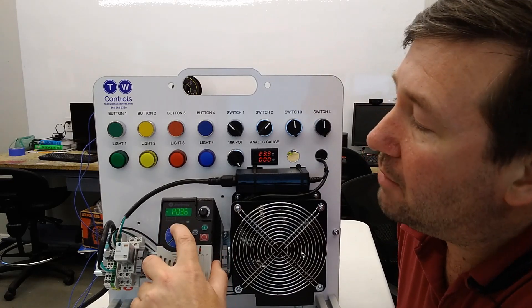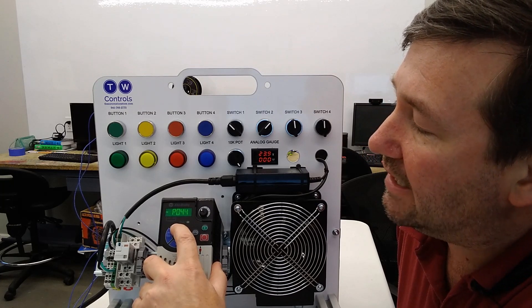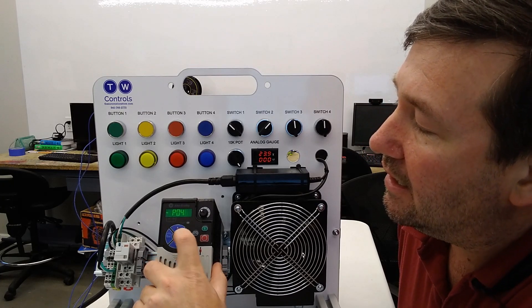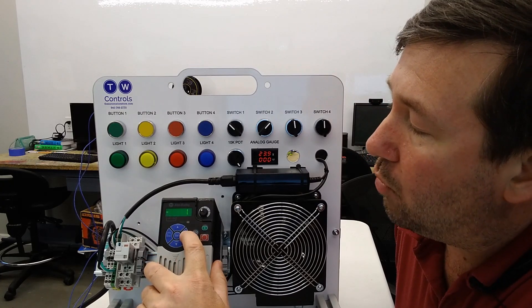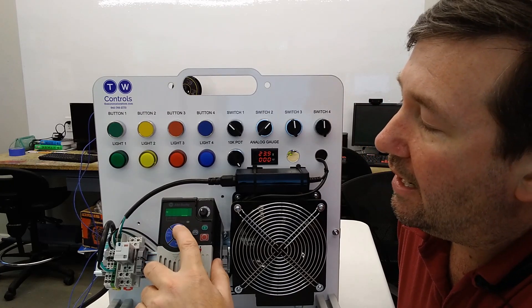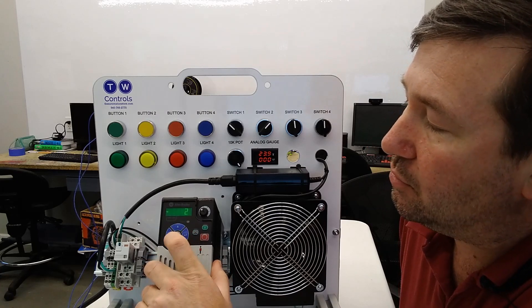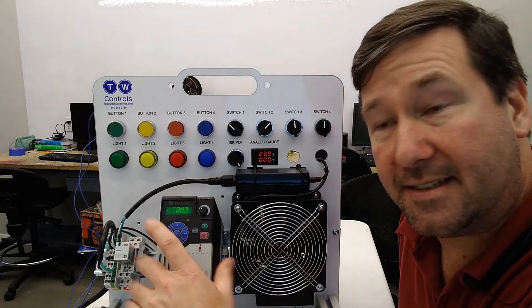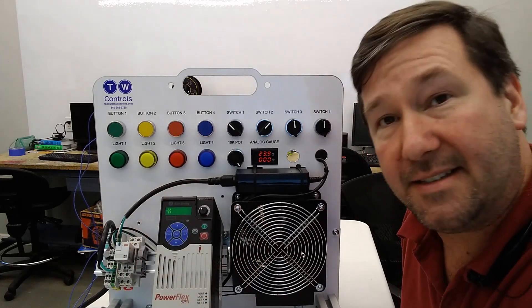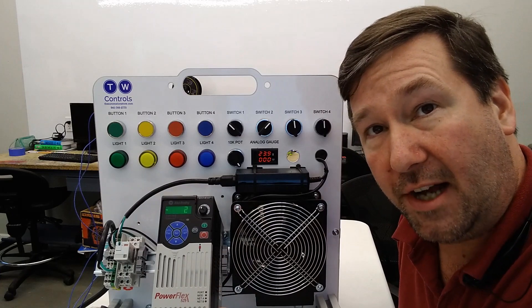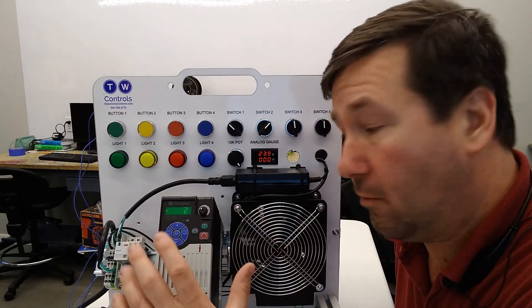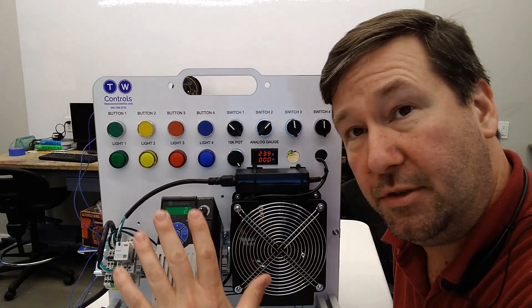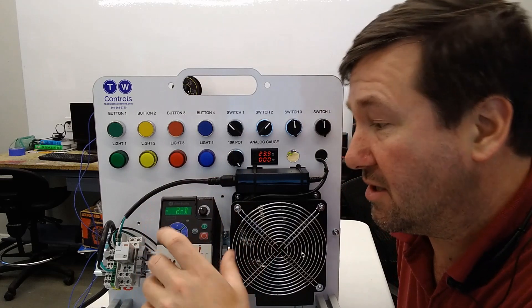Now we're going to go up to P46. It is currently set to 1, and we're going to move it up to 2. That's going to set our start source as these terminal blocks. Now we need to configure input 1 and input 2 for that start stop.